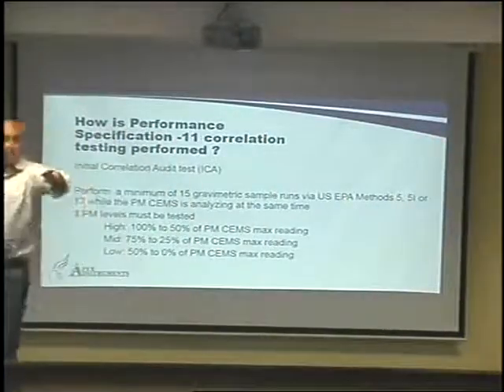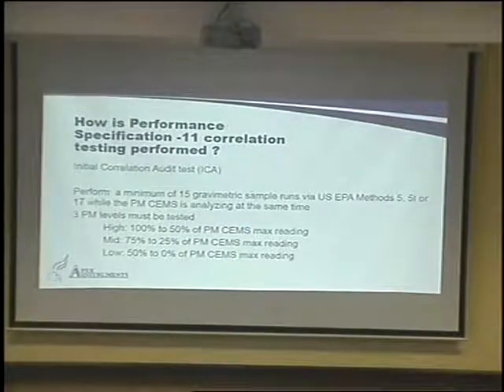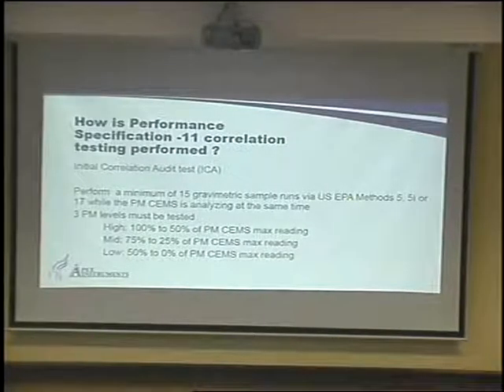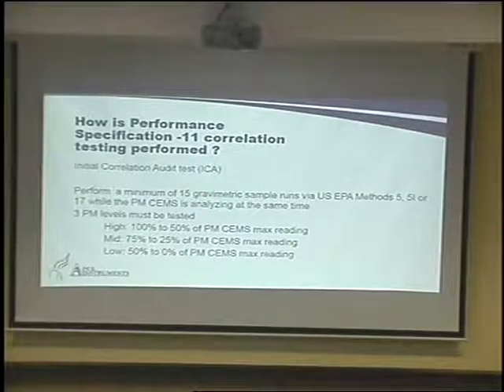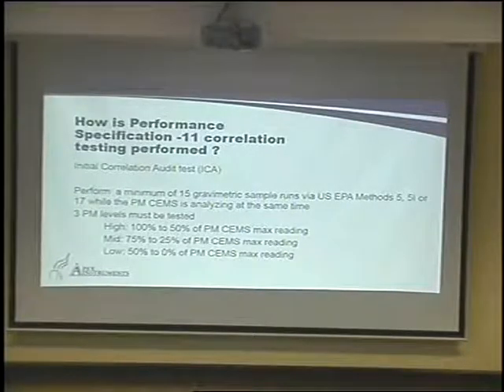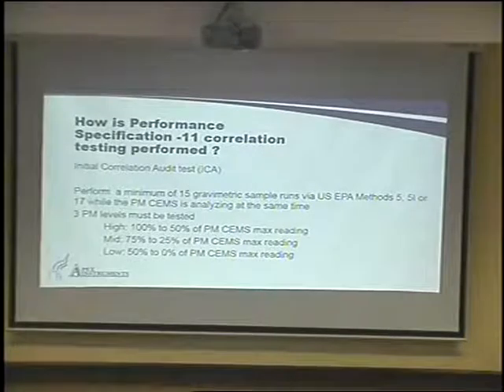Within those 15 runs, you should be testing three different PM load levels. You should be testing 100% to 50% of the maximum of the PM CEMS unit, and that will change depending on technology and manufacturer. If the instrument can read 25 micrograms per cubic meter, we need to be testing between 25 and 12.5 to really test that instrument.